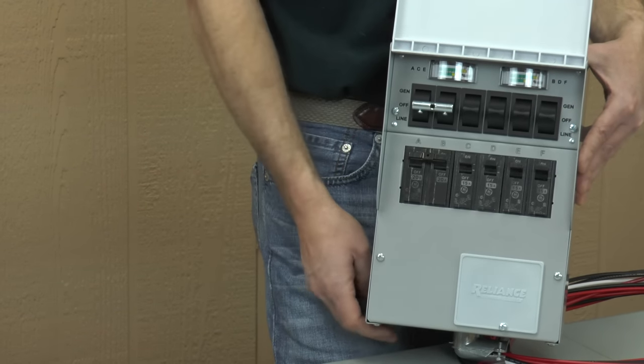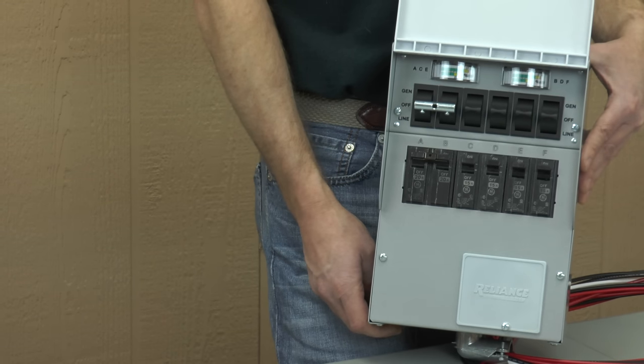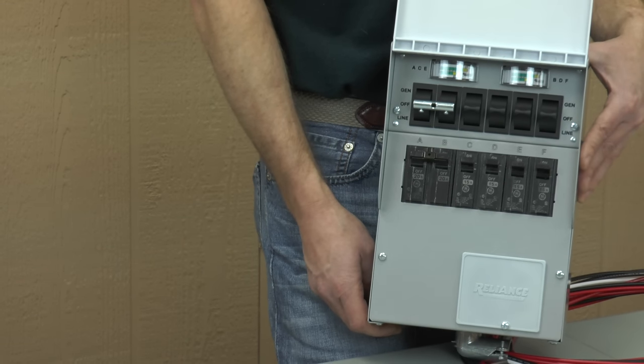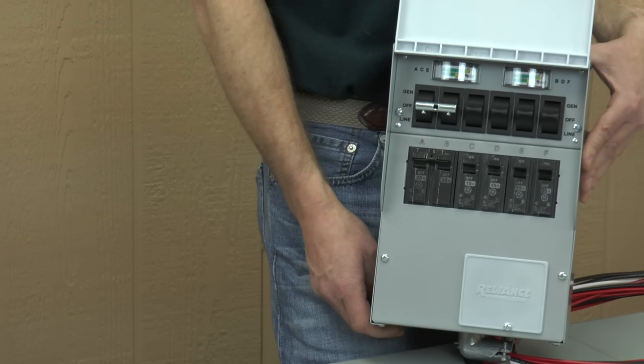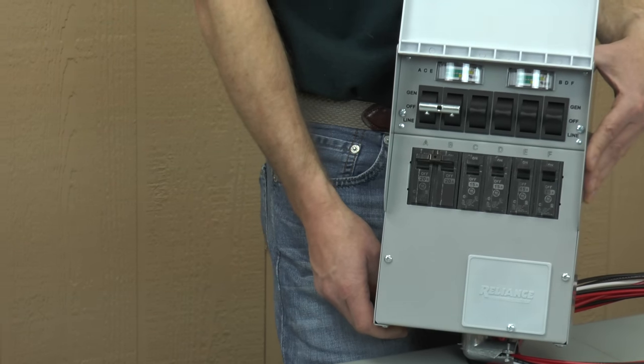There's a chart in your installation manual that shows the wattage requirements for many typical household devices. When choosing which circuits to operate, try to divide the total wattage evenly between the two sides of the transfer switch.